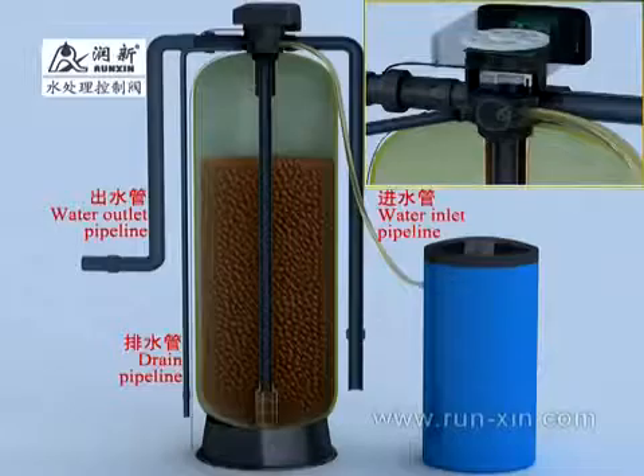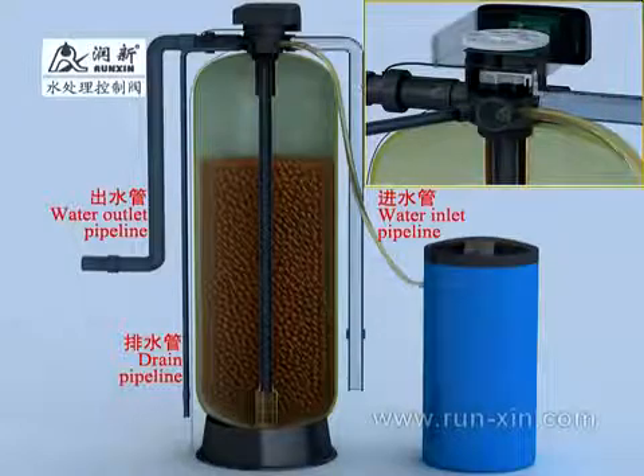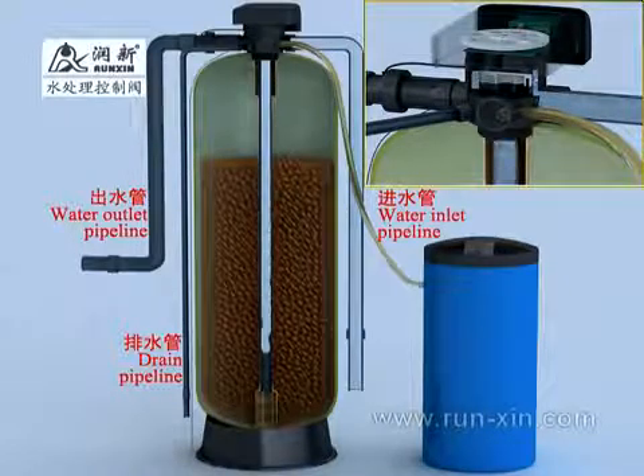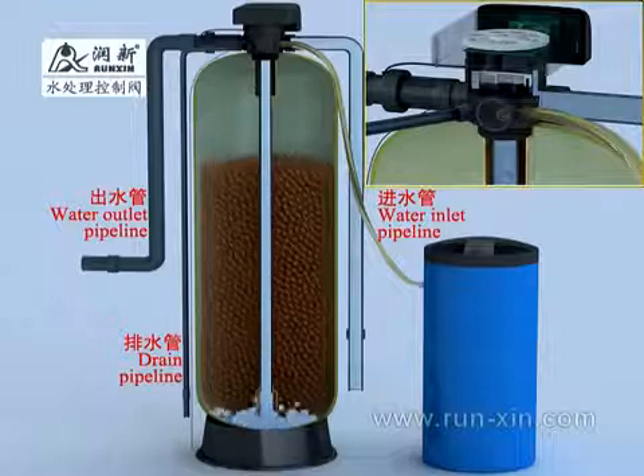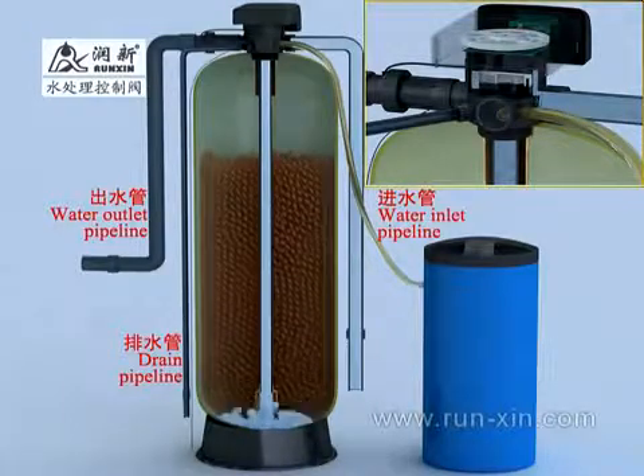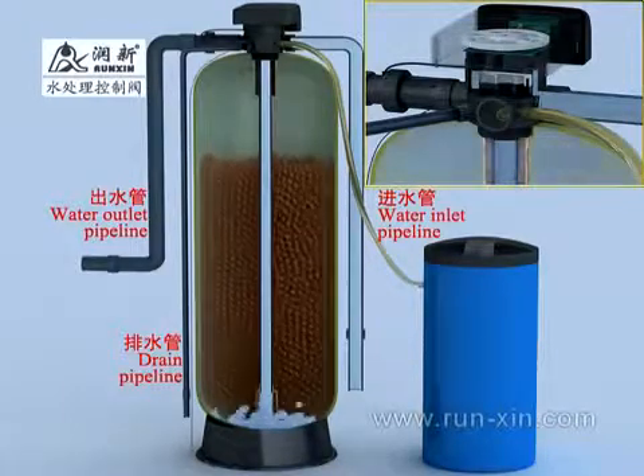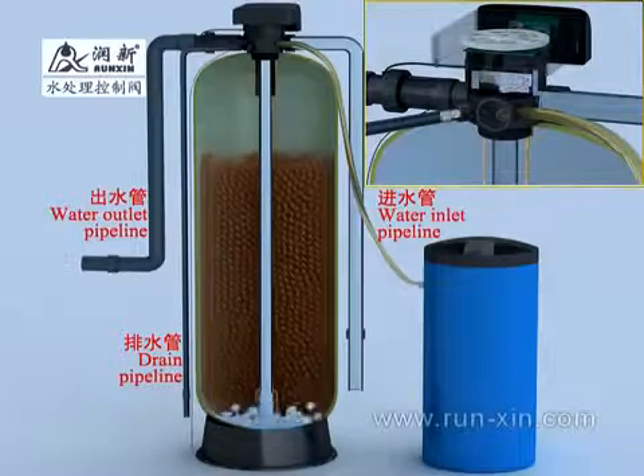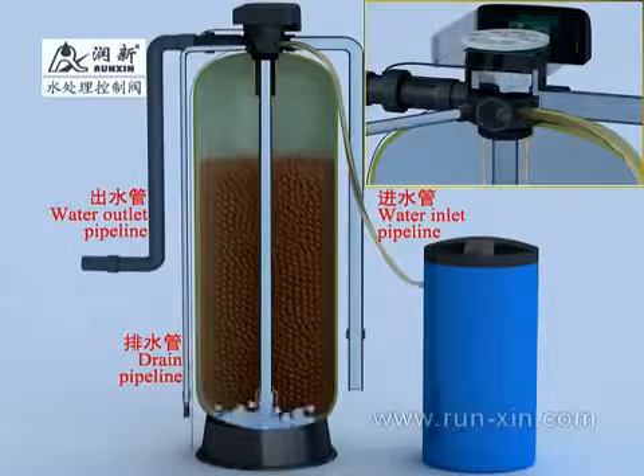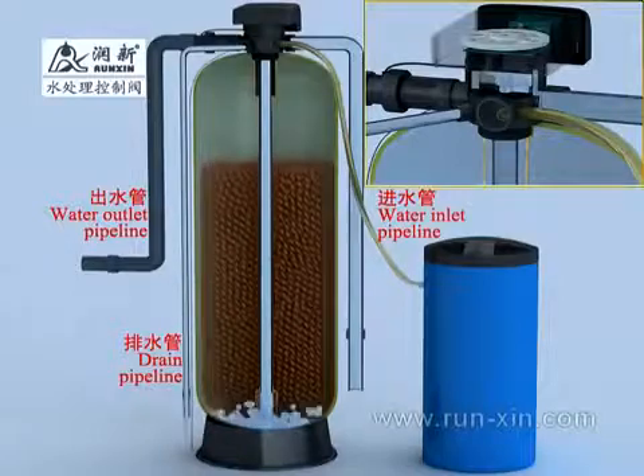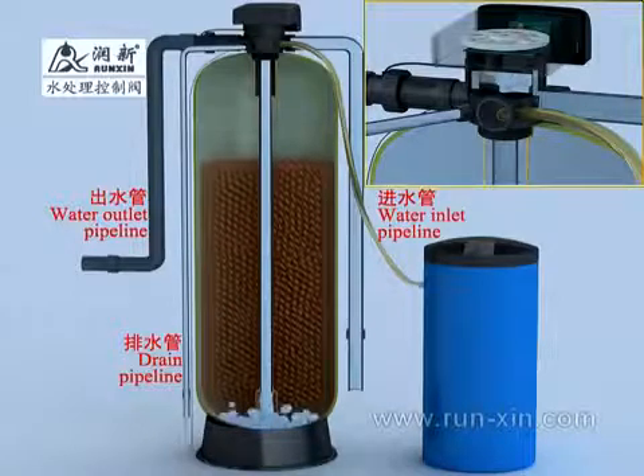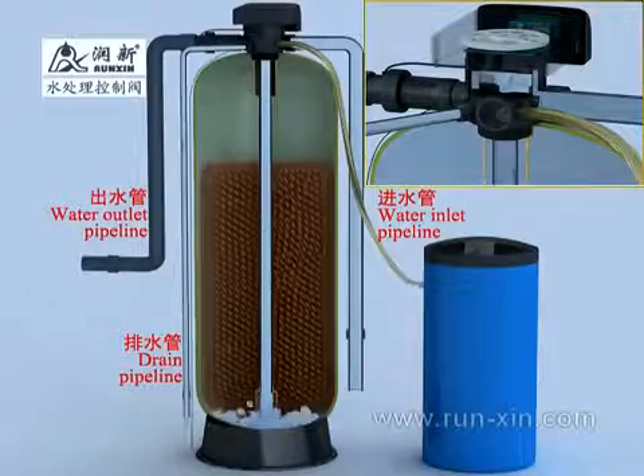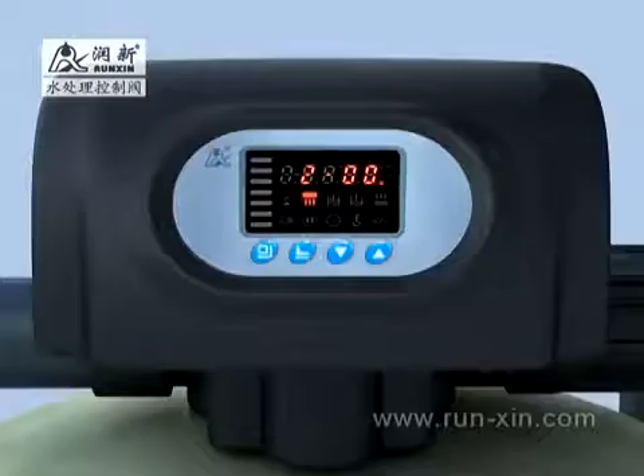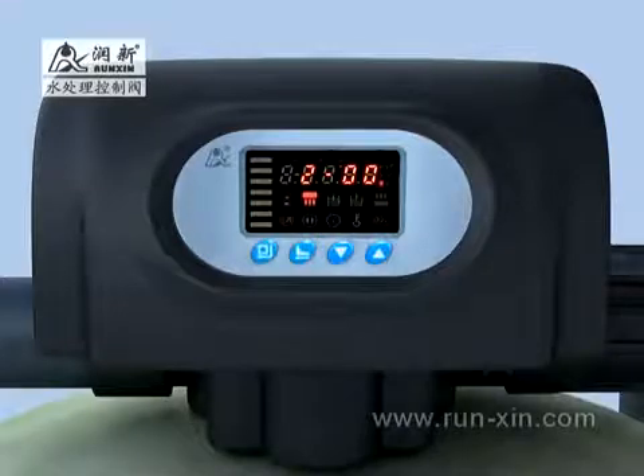Raw water flows into the control valve through the water inlet, from the top of the valve core, through the riser pipe to the bottom of the tank, then through the bottom strainer into the tank. Under the influence of water flow, the resin layers are loosened. The broken resin or dirt flows out from the drain outlet. When backwash time reduces to 0, it is over.